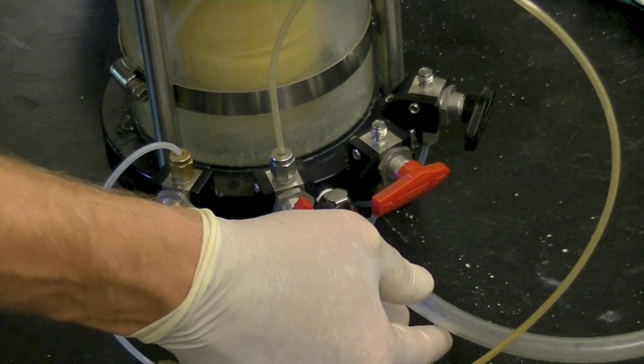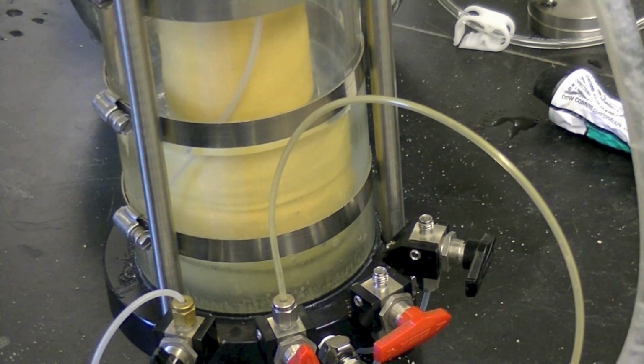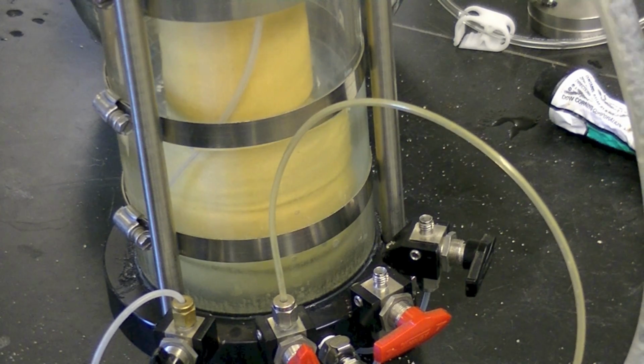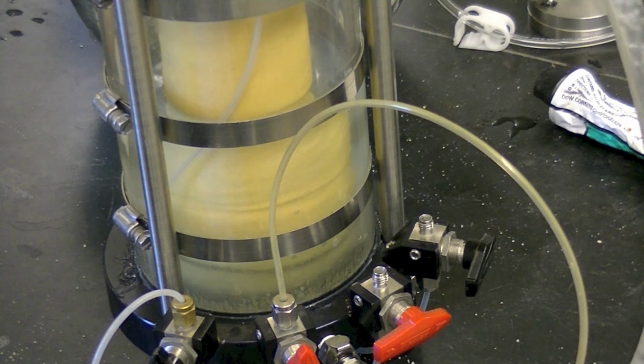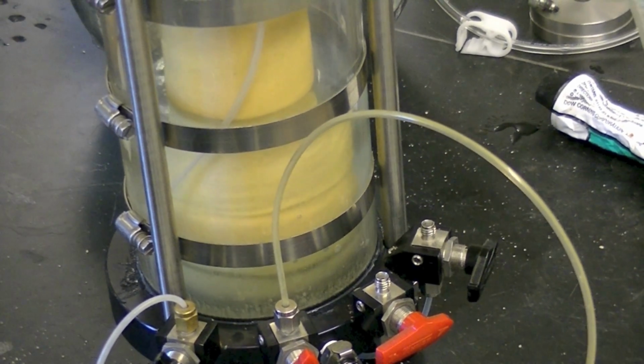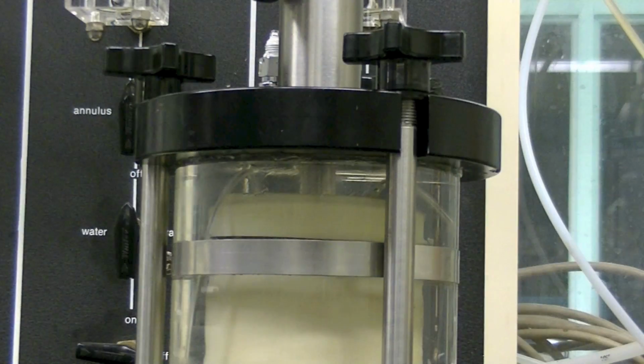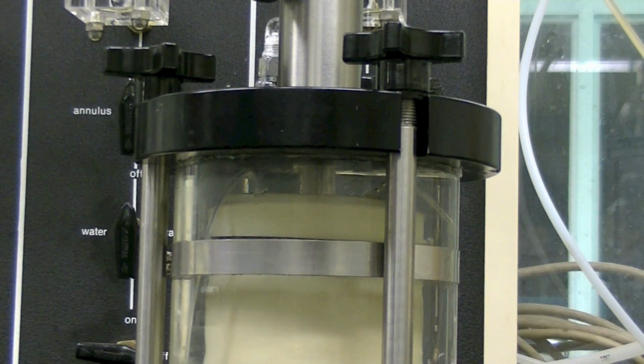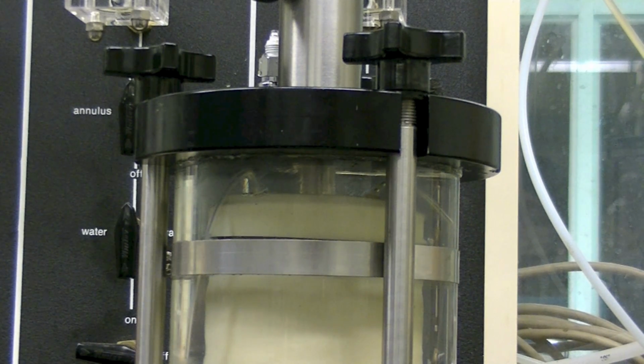Connect the fill valve with the fill hose. Fill the chamber completely with de-aired water. An air release should be open at the top of the chamber to ensure the chamber is completely filled with water. Once water begins to come out of the release, close the air release valve, turn off the fill water and the vacuum.